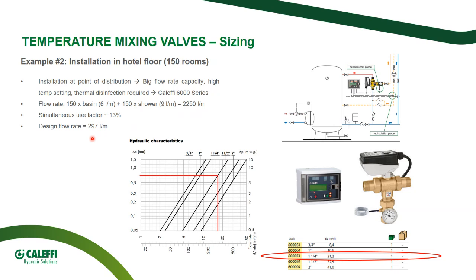It means that my design flow rate is not 2,250, but 297 liters per minute. In the same way, we go to the Caleffi 6000 series technical data sheet, and to the hydraulic characteristic chart. We enter with the design flow we just calculated, 297, and we notice that for 1.25 inch, the electronic mixing valve pressure drop is around 0.7 bar, so 7 meter water gauge. That is fine. So the correct size for this application is 1.25 inch. Never mind if the pipe that I calculated is bigger.